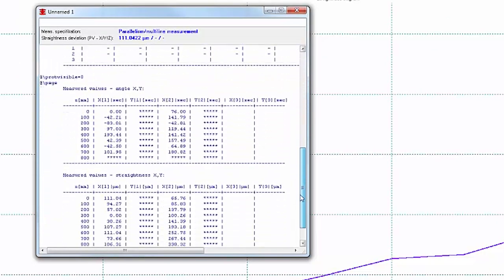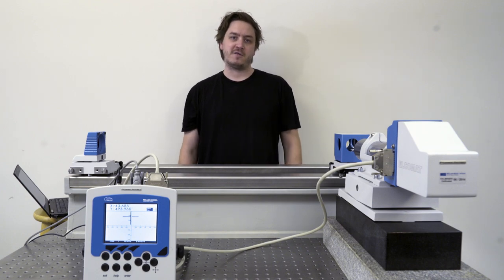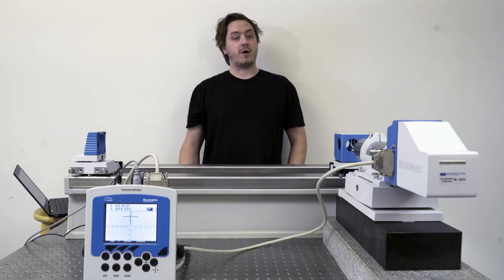The Elcomat 3000 is very well suited for this task because of its long working distance capabilities and its very high accuracy. With a working distance of up to 25 meters, it is able to measure very long rails. With its accuracy of one quarter arc second, the Elcomat 3000 is able to measure differences in straightness on the order of 10 microns.